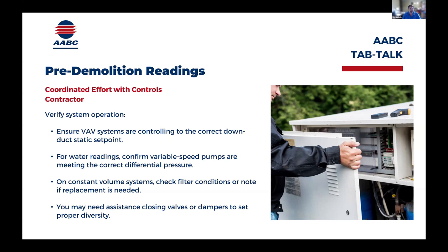When something like that happens—and I think we'll speak of this in future slides—the comfort of existing occupied areas may come into play if you were to dump a hot water system, or even dump an air handling unit to full cooling. Maybe chillers or boilers will have to be turned off and different things manipulated. It could range from a pre-demo reading of a couple VAV boxes and a few grills, all the way to an entire hot water system, chilled water system, various air handling units, and multiple VAV boxes.